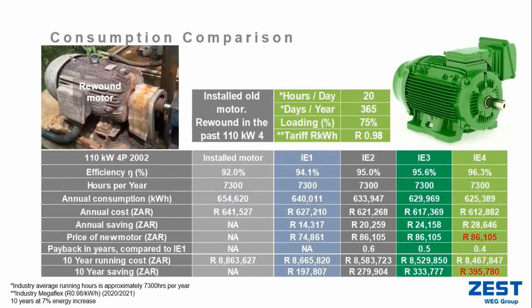But we went to look at the same motor, a 110 kilowatt 4-pole motor. And this motor was installed, it's still running. It was installed in 2002. So a typical electric motor has a design life of around about 20 years. And we looked at that motor when it was designed. Efficiency on the motor was stated at 92%. We looked at the hours of the motor running per year, around about 7,300 hours per year.